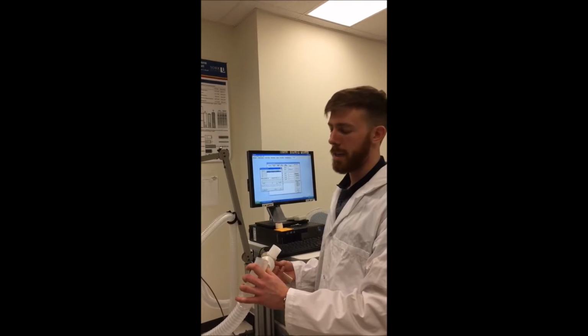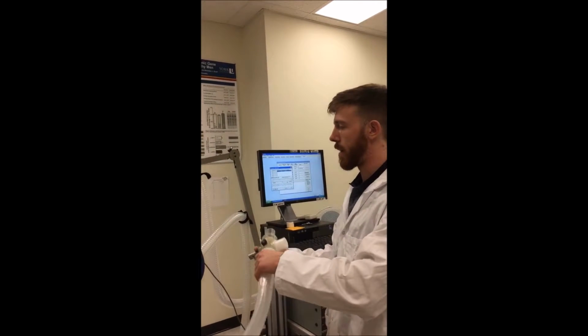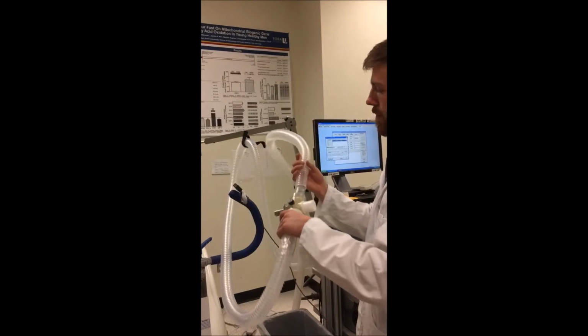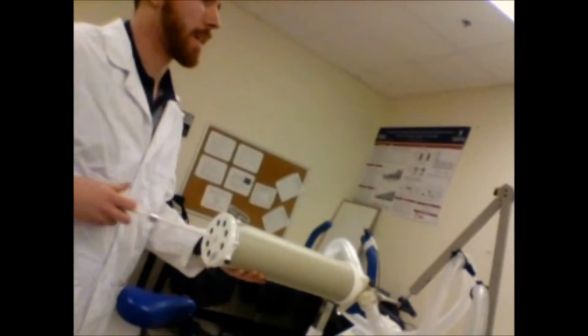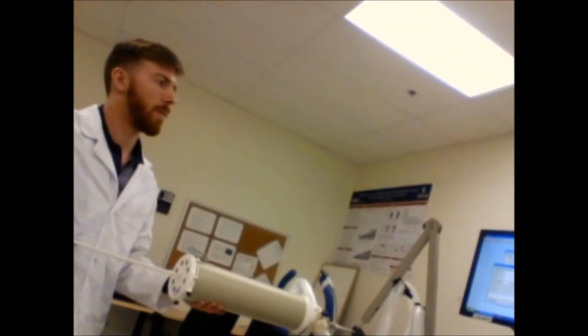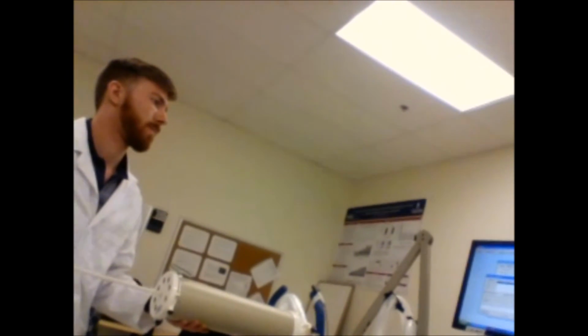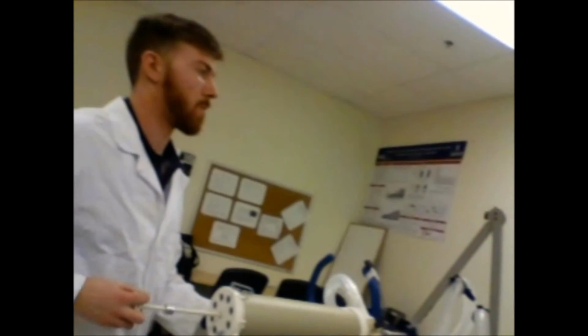Next, for the pneumatic calibration, you're going to attach the tubes so that the air is directed into the system. The purpose of this part of the calibration is to provide the system with a predetermined mass flow of gases to be detected and measured. The syringe is used to pump air into the system in order to verify the performance of the transducers within the air inlet. Next, you click pneumatic calibration and pump with the syringe. The aim of this is to get 5 consecutive strokes within -1 and 1% error. Then you click verification and repeat that same process over again.